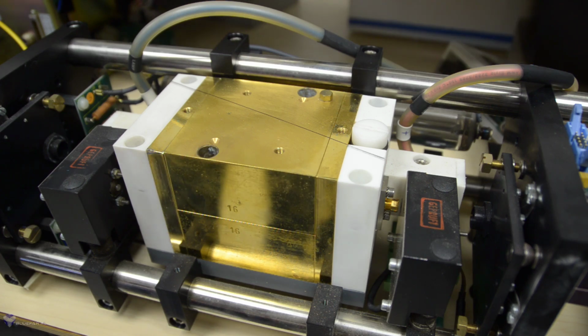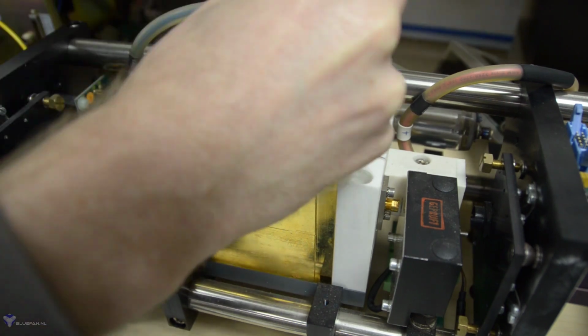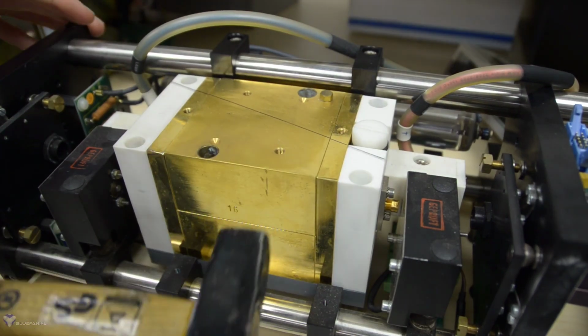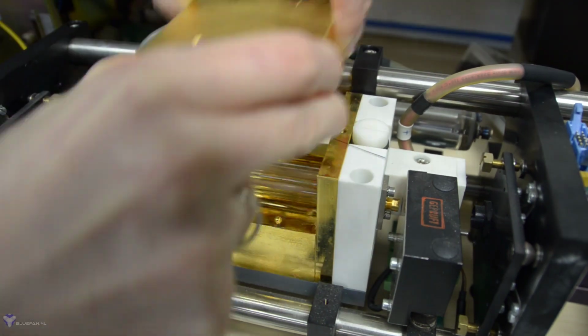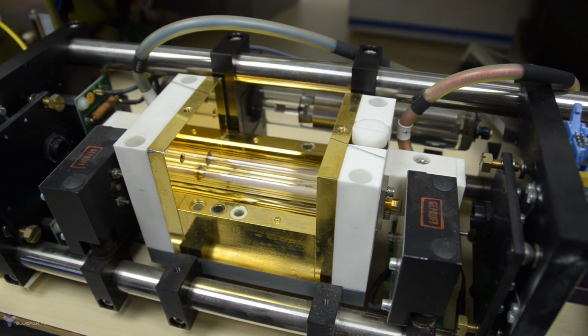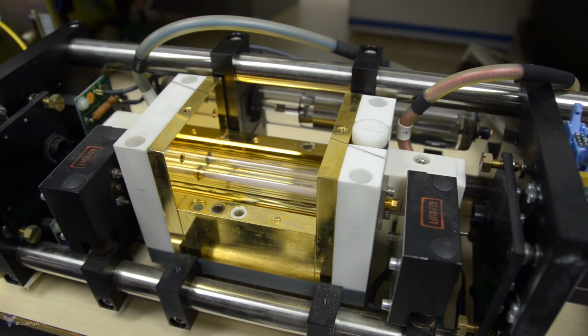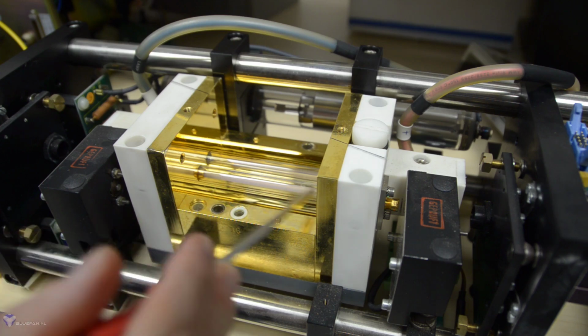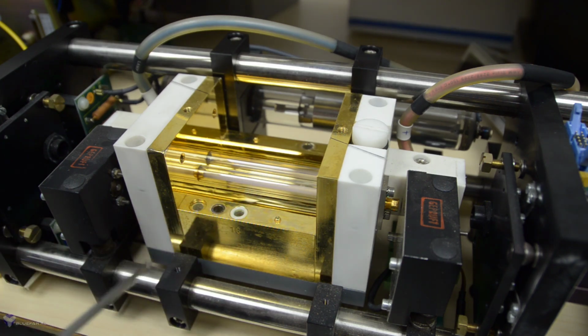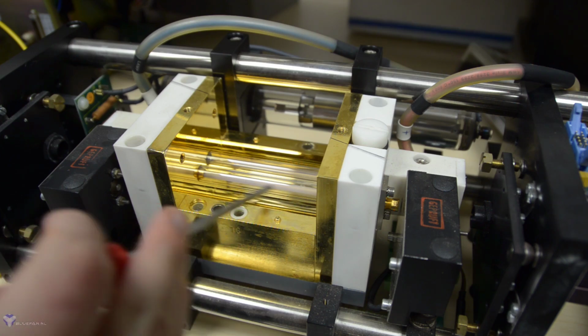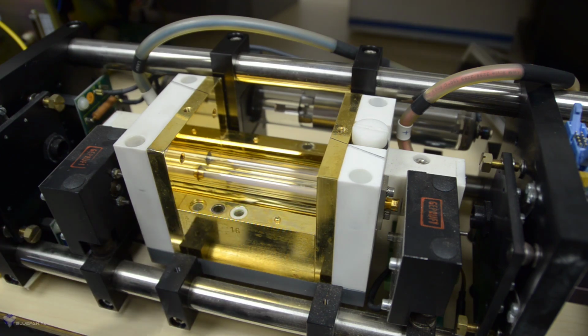The laser is water cooled and I've seen more than one laser that was pretty contaminated and ugly on the inside. So I want to check if everything is alright. And there you go, the inside of the laser head. Now it looks really cool. And we have here at the front the neodymium YAG rod enclosed in a flow tube. And the water flows inside there to cool the YAG rod, because a lot of power gets dumped into it, a lot of optical power, which means that it heats up and it needs to be cooled away. Otherwise it heats up too far, it fractures, or you get a lot of thermal lensing.